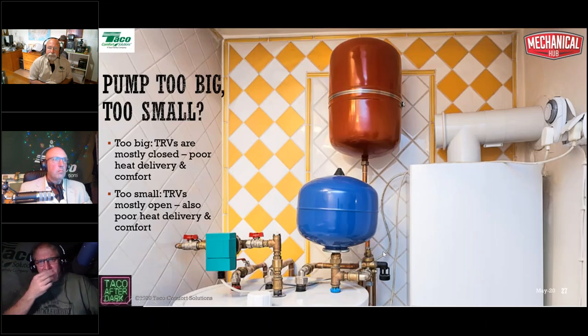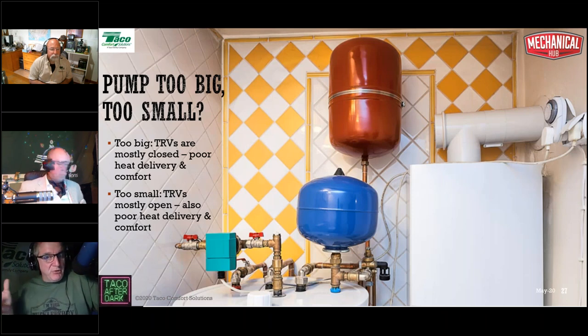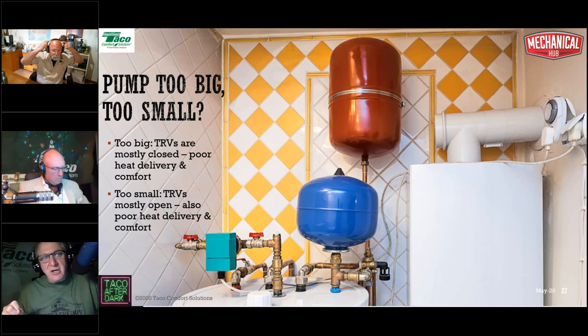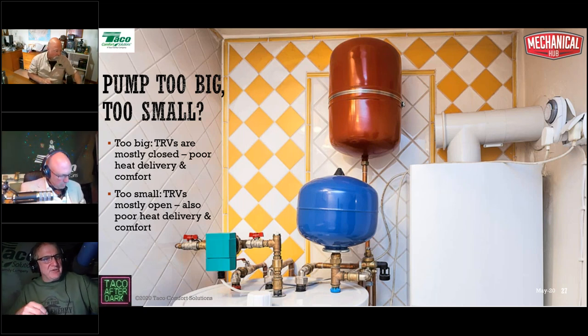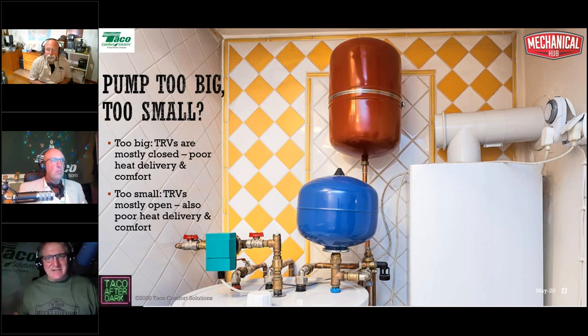So in that situation, if you have a pump that's too big or too small, both create issues. If the pump's too big, the TRVs are mostly closed, and that gives you poor heat delivery and comfort. If the pump is too small, the TRVs are mostly open, which also is poor heat delivery and comfort. It's not terribly consistent in either respect.